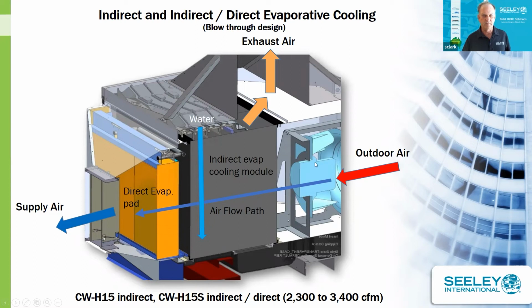I should also mention that these fans are variable speed. So we can control them at a variety of speeds and airflows. In addition, we can turn the pumps off, and this unit can be a ventilation unit for outdoor air economizing. And then the supply air comes in to the space here. So this is what we call our blow-through design.